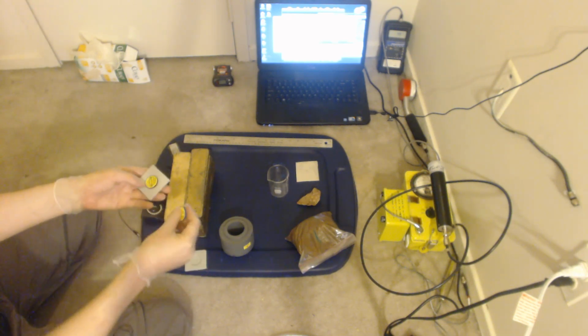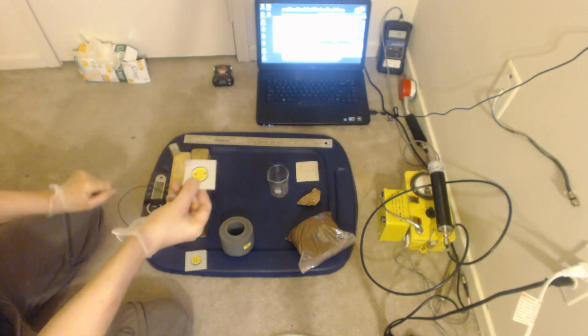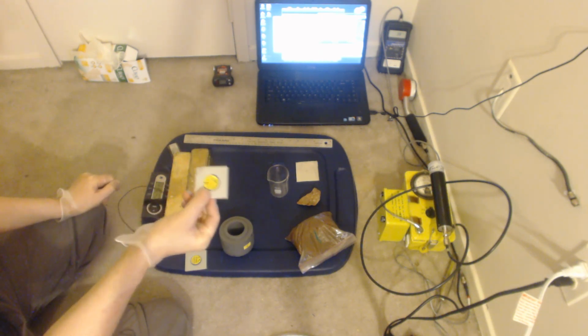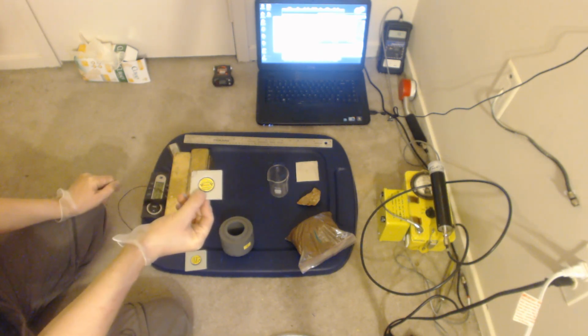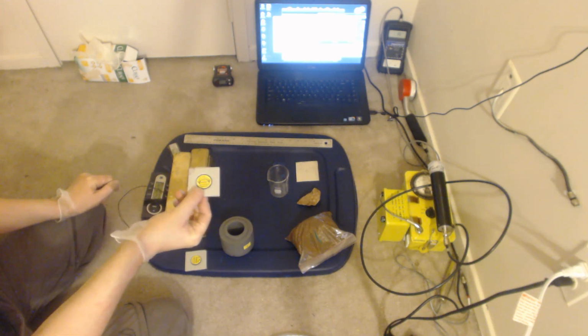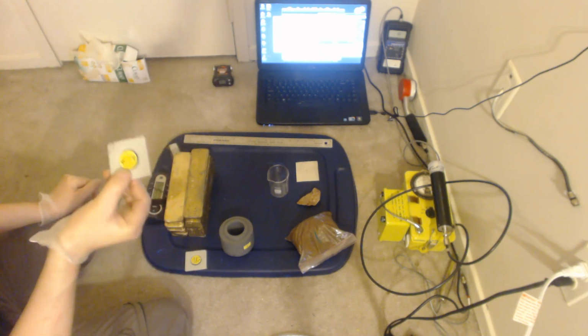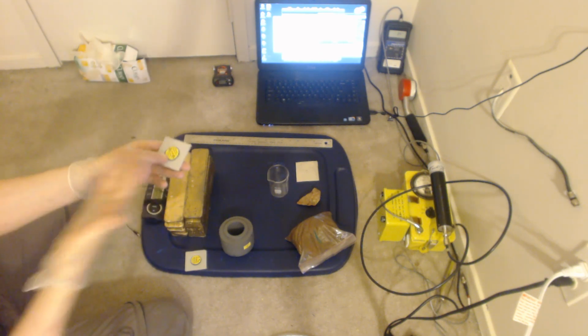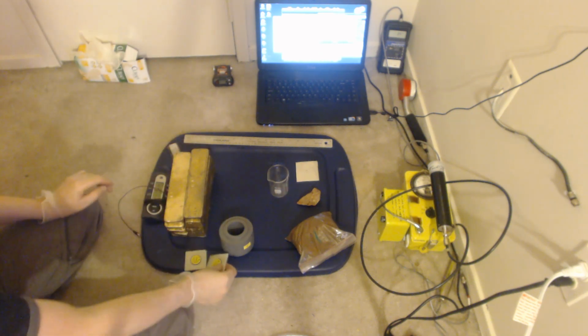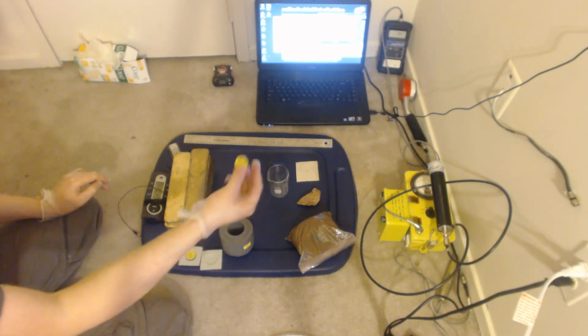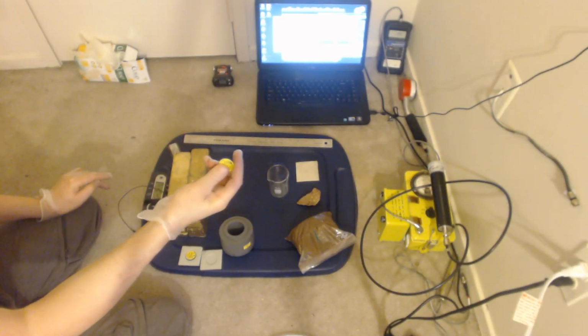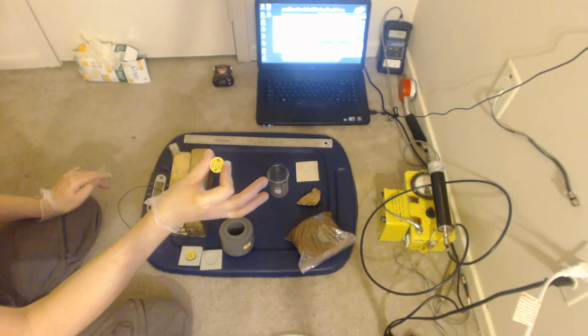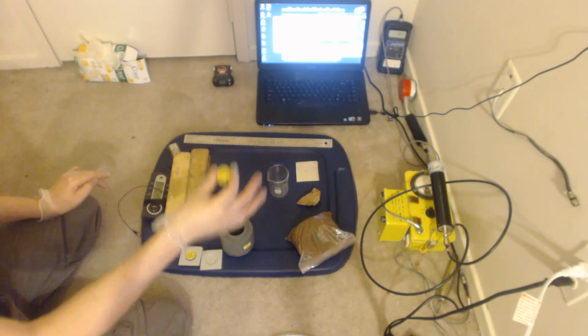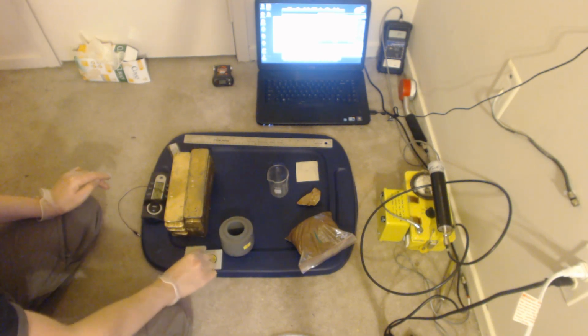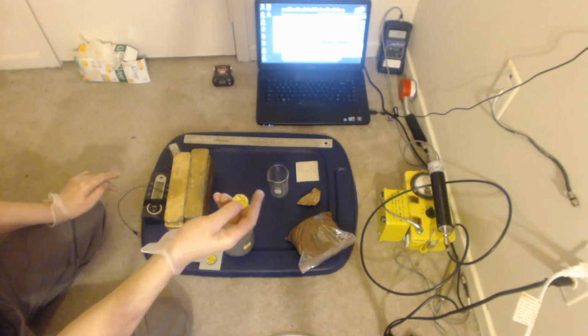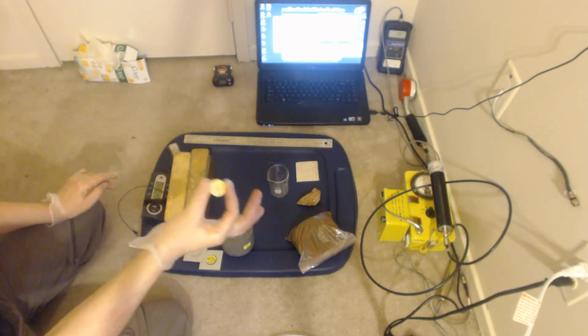I recommend cesium-137. Here's 2 samples of it. Cesium-137 produces 2 beautiful energy lines, one at 32 kiloelectron volts and one at 661.66, right across the board. It's almost like nature made us the perfect calibration source. The difference between these two is that this one is 80% accurate on the amount that's in it, plus or minus 20%, and this is about 37 kilobecquerels. This one has been assayed to 95% accuracy, so plus or minus 5%.